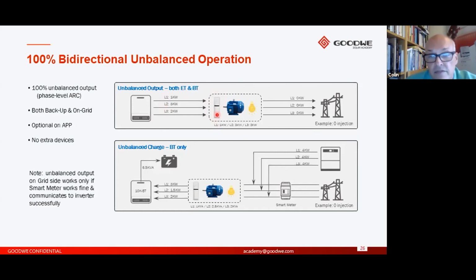So what you can see here is that now, as we've only got 1 kilowatt being produced to each of the phases, for phase 2 and phase 3, we now have a deficit in energy being produced from the inverters. So that means you're now going to have to draw energy from the grid to support these loads. So obviously that isn't very good. So that's why we have the feature of unbalanced output. Now, when you set that mode, what that means is you can now actually control exactly the demand from each phase individually to supply to the demand on each phase of the load side, with still maintaining no export. So that's why we've got this capability here.